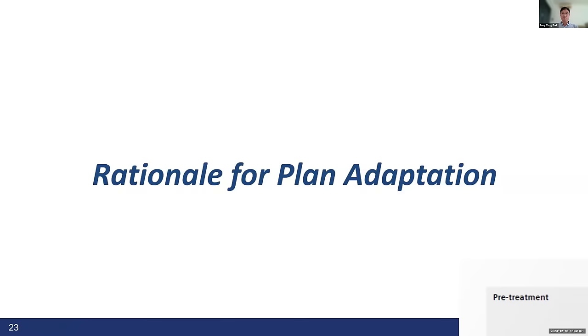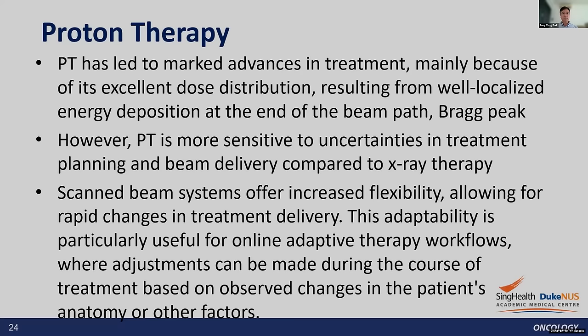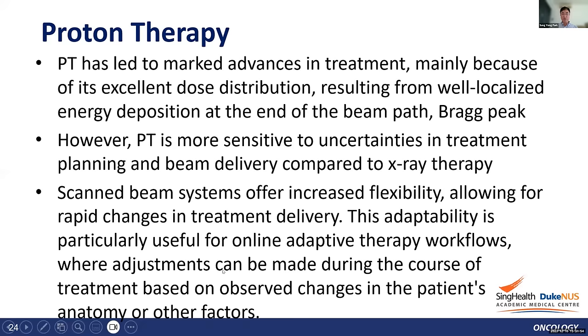Regarding the rationale for plan adaptation: proton therapy has led to marked advances mainly because of its excellent dose distribution from the well-localized energy deposition at the end of the beam path — the Bragg peak. However, proton therapy is more sensitive to treatment planning and delivery uncertainties compared to X-ray therapy. The recent pencil beam scanning systems offer increased flexibility because we don't use apertures and compensators, allowing for rapid changes in treatment delivery — particularly useful for online adaptive therapy.